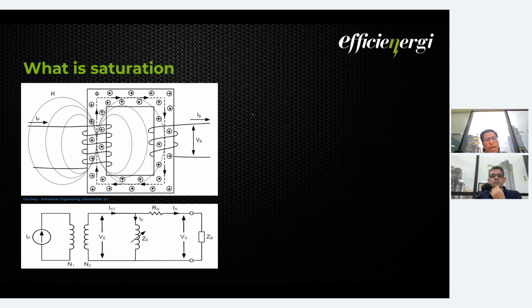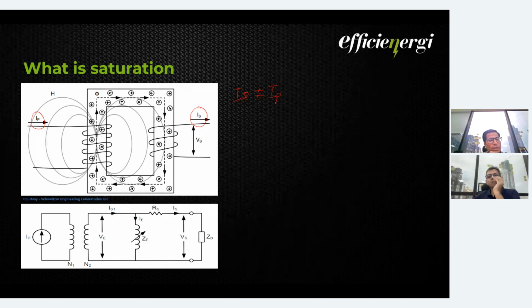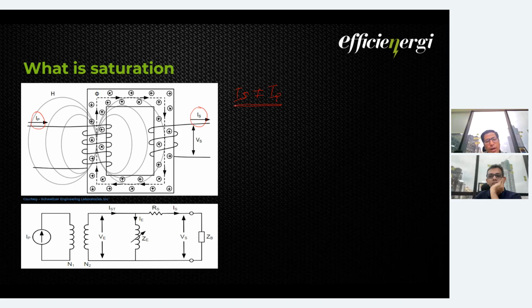So now everyone knows the saturation means the core gets saturated. The core gets saturated means the flux inside the core, that is the flux density of that particular core material or the core size, is completely fulfilled, that is saturated. So here, basically, in terms of current transformer, what we are saying when there is a saturation means, here you can see this is your secondary current and this is your primary current. So when the CT gets saturated, that means your IS is not equal to IP. So whatever secondary current is seen by the relay will not be exactly equal to what is actually the fault current or what is actually the abnormality seen in the primary. So this is the main reason we have to take care of the saturation, because the actual fault current will be different, and the current sensing at the relay will be different if this sensor, that is the current transformer, is not working in its unsaturated zone.